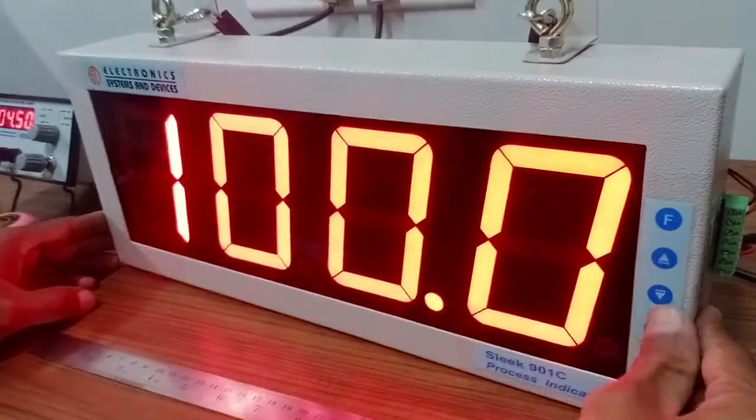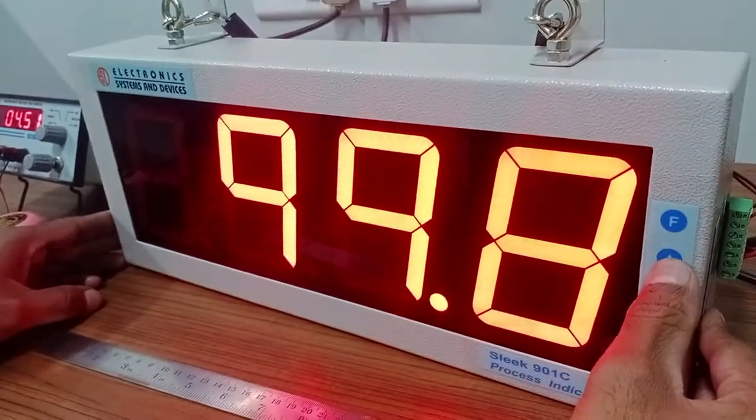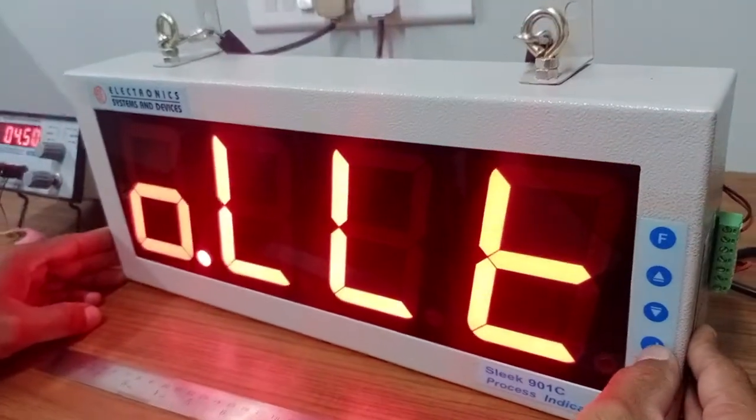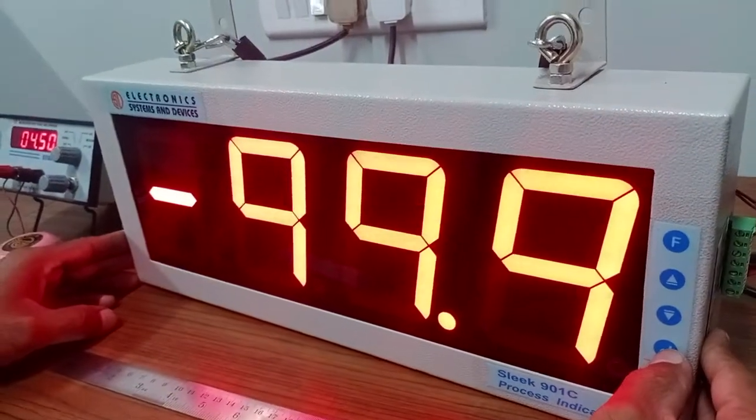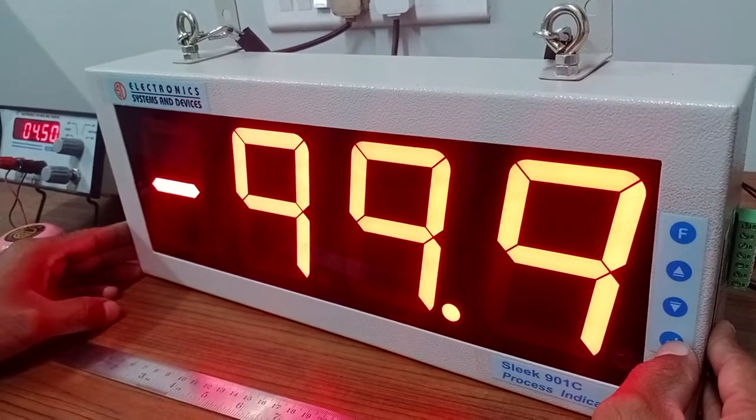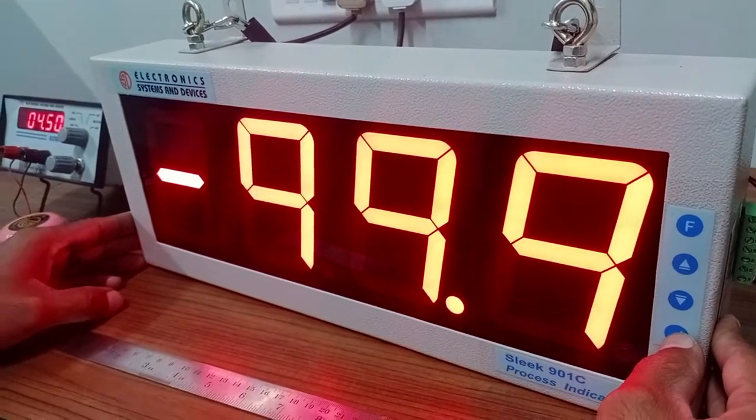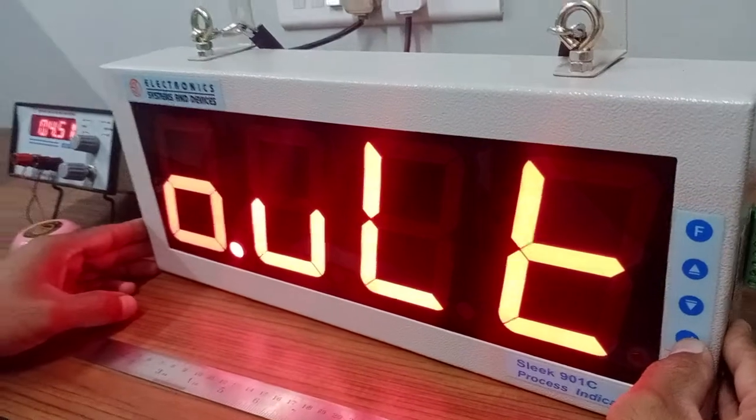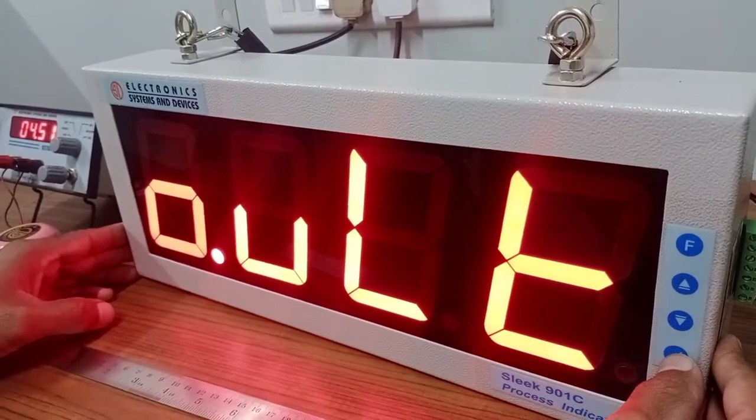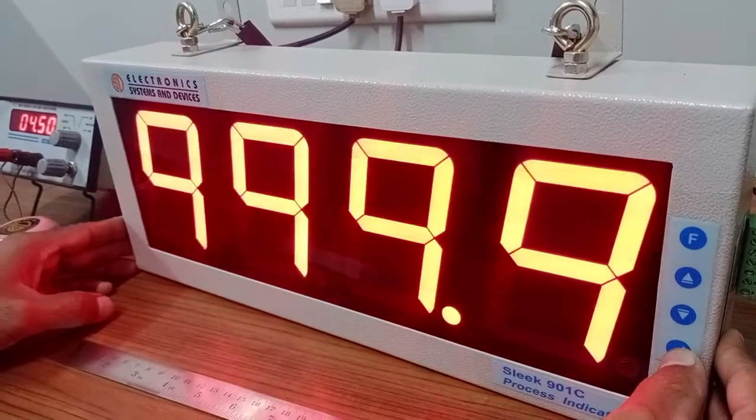Enter. This is output lower limit which is for retransmission output, like 4 to 20 retransmission output. We will skip that because this instrument doesn't have retransmission. This is output upper limit, again for 20 milliampere of retransmission output.